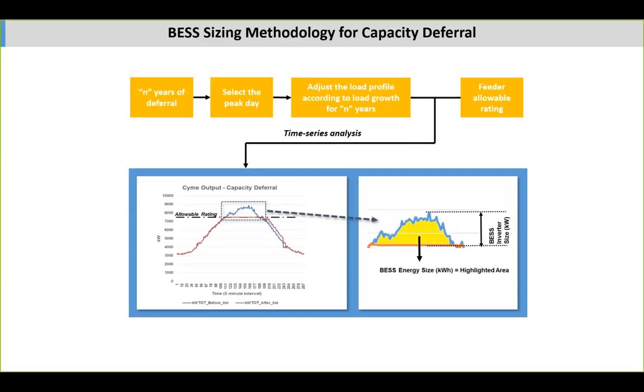Now here's an interesting point you can see by looking at the yellow area under the curve. As we move out in time, if the load grows, the amplitude of the peak grows - that drives the battery power rating, the size of the inverter. So the megawatt or kilowatt size increases typically linearly with time, but the area under the curve gets wider and increases as the square of time. So if we look at the deferral problem, we can ask: what's the best deferral period to aim for?